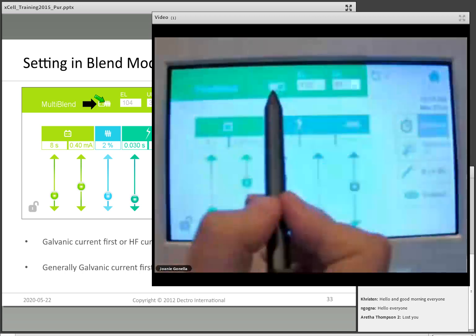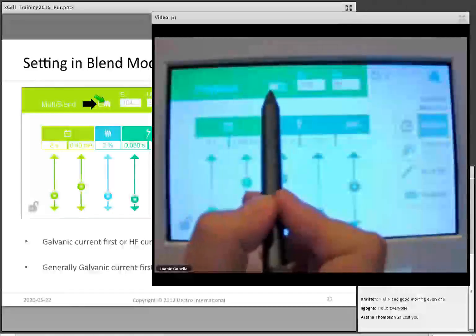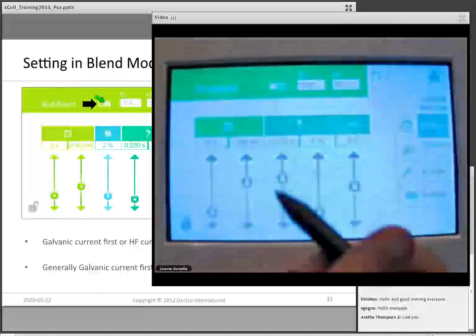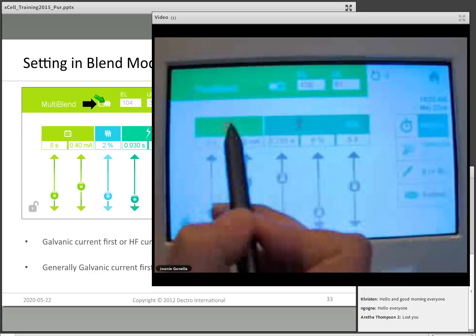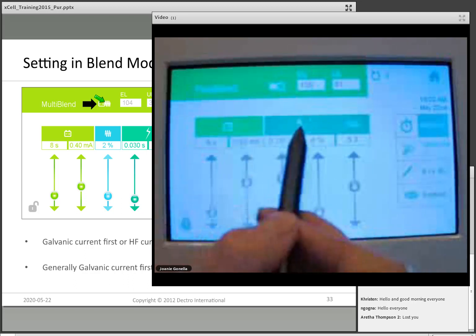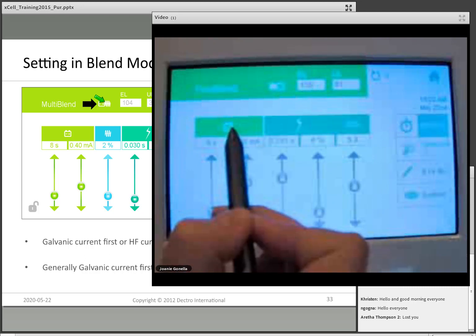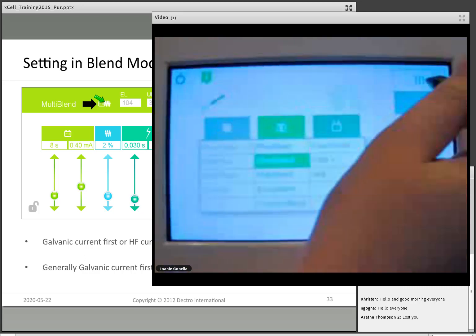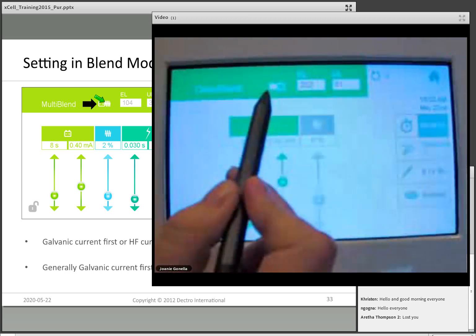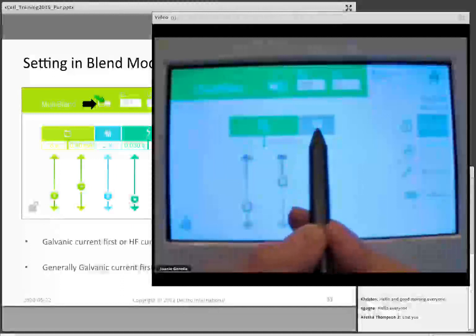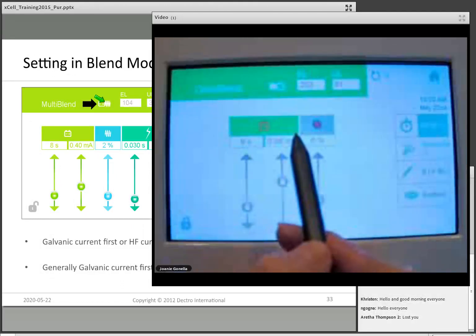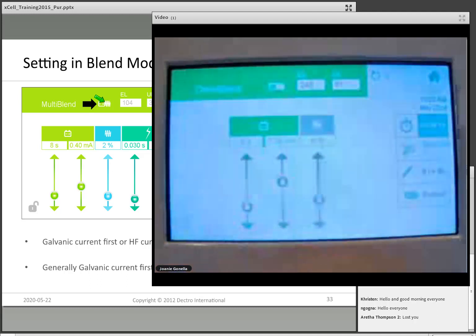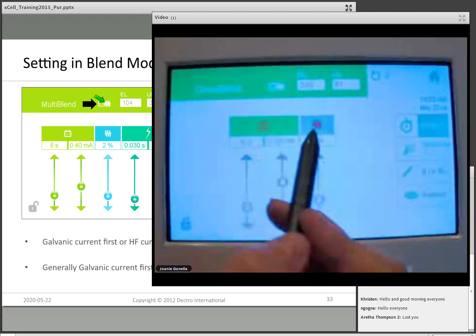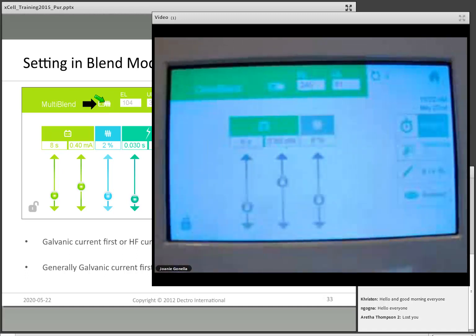by pressing on this, and now it flips it. What you see is the wave first and the battery second. So when I lock this and press on the pedal, you'll see this, then this. It's still pulsing, but I had a pulse of high frequency first, and then the galvanic came on second. MultiBlend, same thing. It remembered my lead here. So now when I press on this, I should see this first, marginally, and then after that you see this, because they're both sort of continuous, so they almost turn on at the same time. If I switch this, unlock, switch, lock, then I had battery first, and then I had the high frequency. So that is the leads.